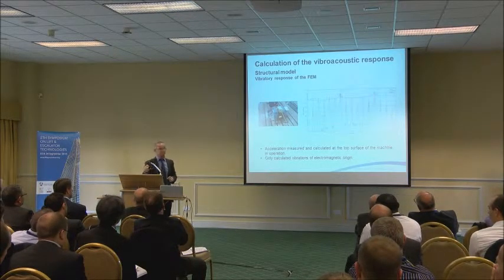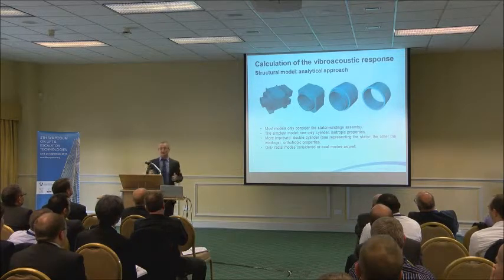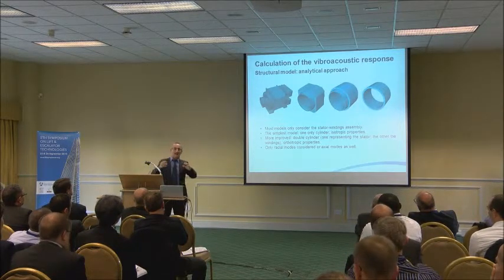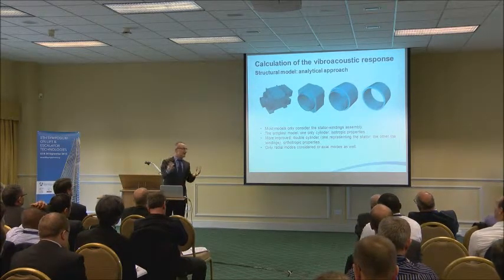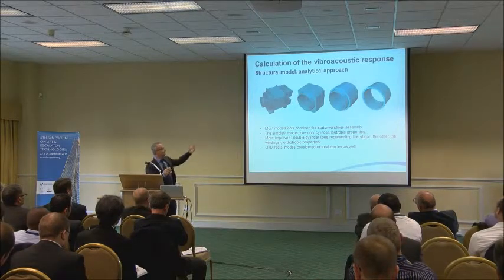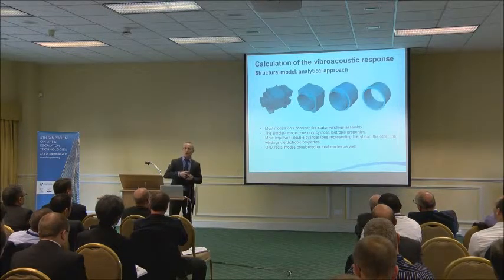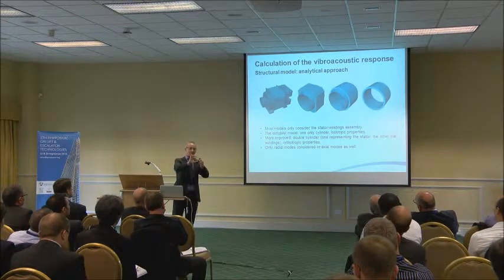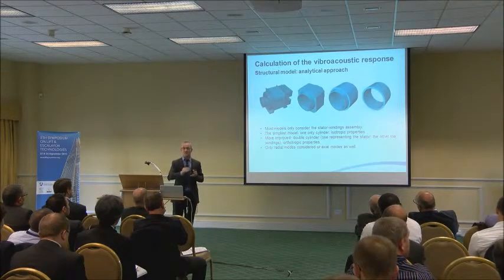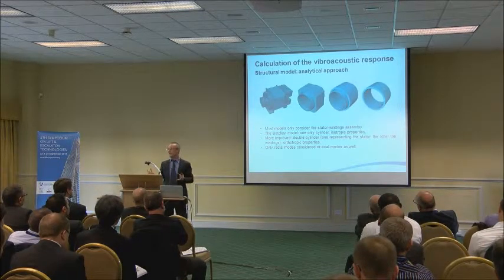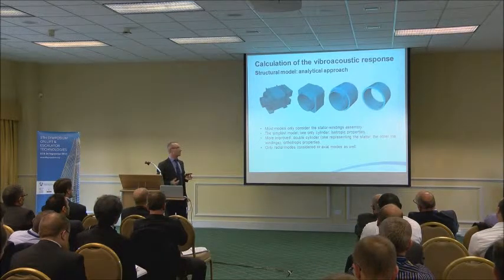Concerning the analytical models, the usual analytical models only take that part out of the air gap. That part that consists of the stator and the winding. So the usual approach is considering, well, I am going to neglect all axial modes, and so I am going to model it as a ring, a two-dimensional model, where you consider only radial modes with isotropic properties.